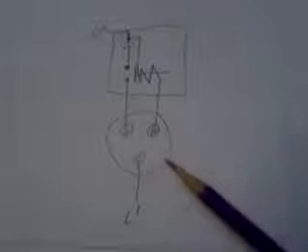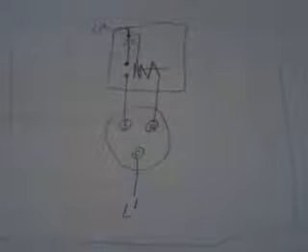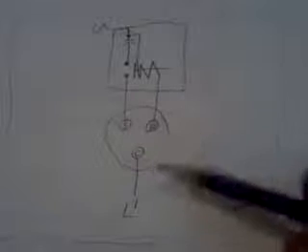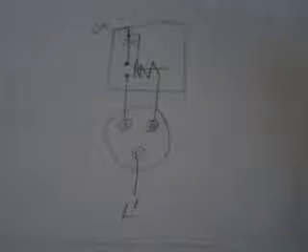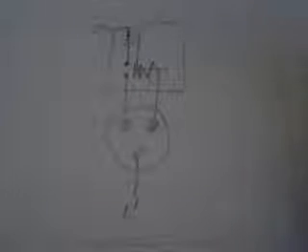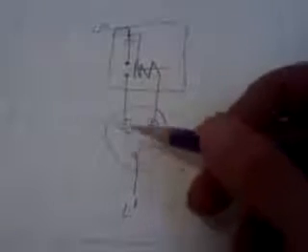Let me read from this here: as the speed of the motor increases, the amperage decreases. At about 75 percent speed, the amperage will be low enough to drop the contacts. Okay, so what that means is the motor starts and right at first there will be enough amperage to close this, so the start will be in the circuit.